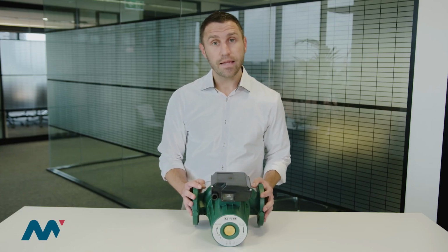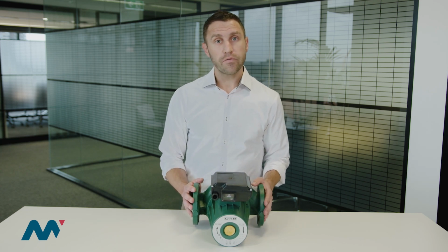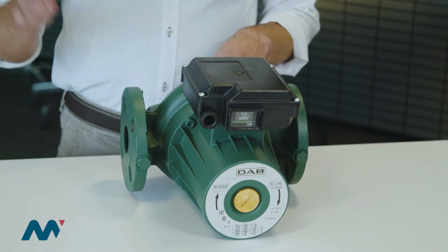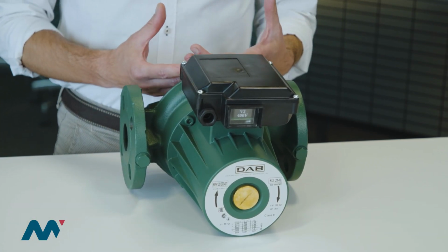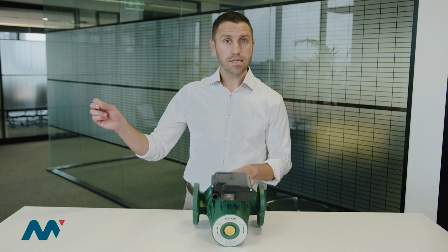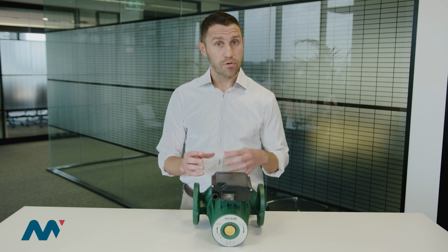Then another main difference of a circulator compared to other pumps is the value of the pressure that they can generate. Being in a closed loop, we don't need that much pressure. We just need a little amount to overcome the pressure losses that the pipeline and the friction over the pipeline create for the flow. Usually, the pressure generated by a circulator is about 5 meters, 10 meters, or 15 meters. It's about 150 kPa.